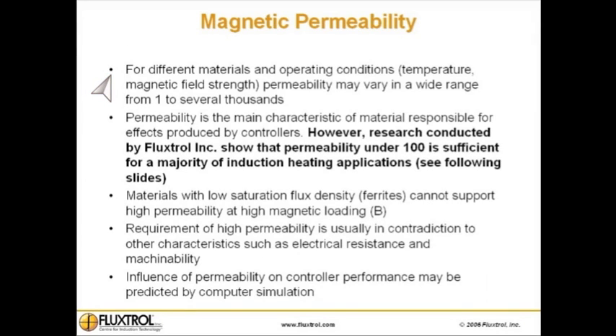Magnetic permeability. For different materials and operating conditions, like temperature and magnetic field strength, permeability may vary in a wide range from one to several thousands. Permeability is the main characteristic of material responsible for effects produced by controllers. However, research conducted by FluxTrol Inc. shows that permeability under 100 is sufficient for a majority of induction heating applications.